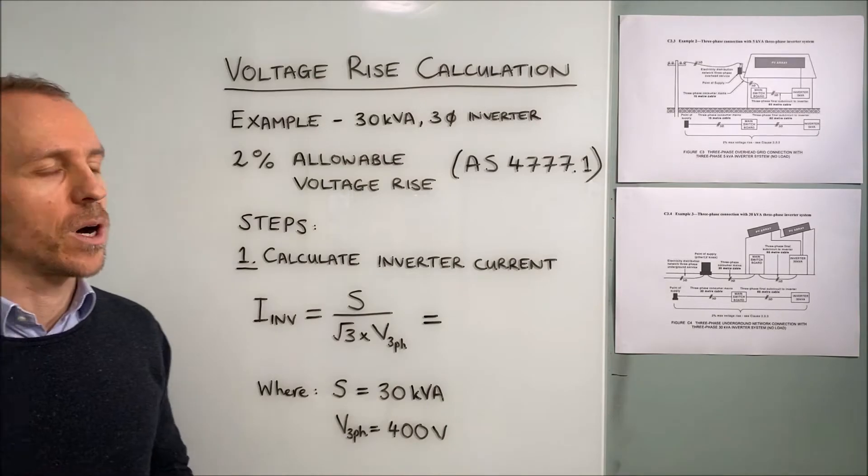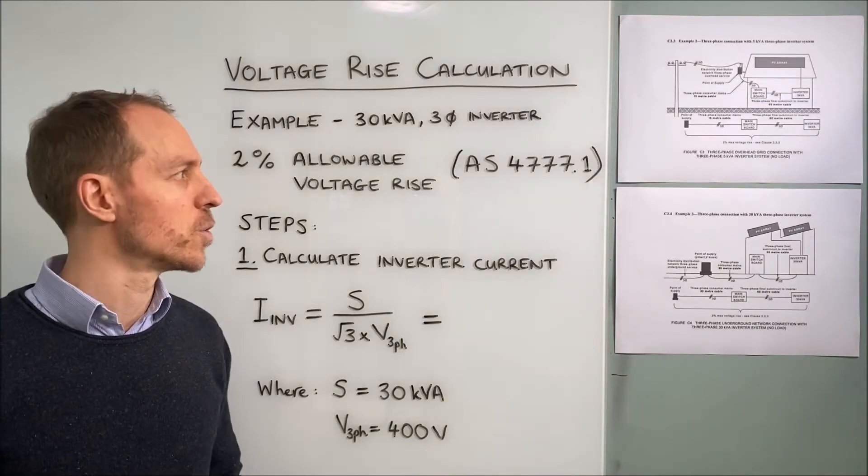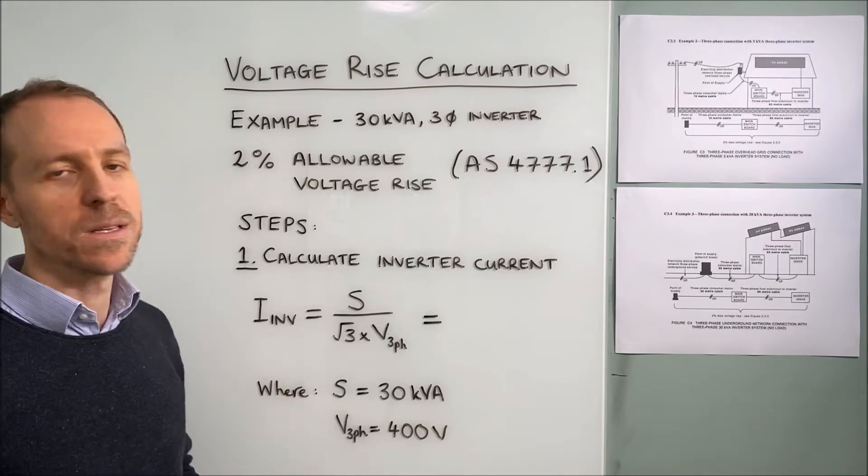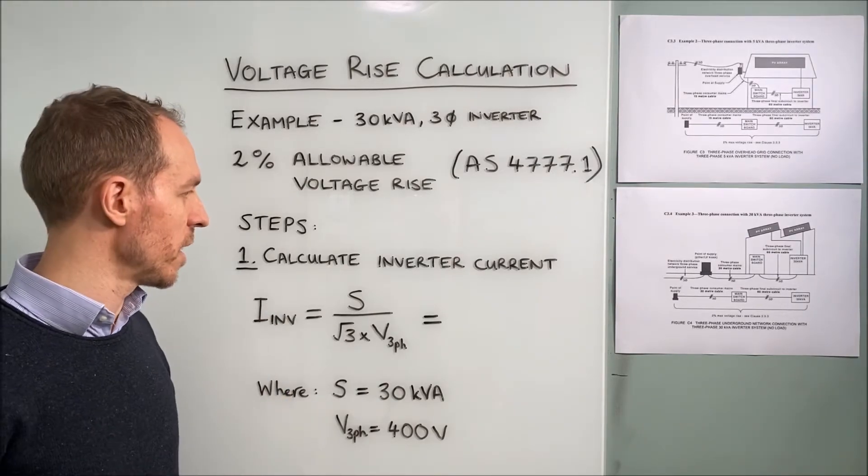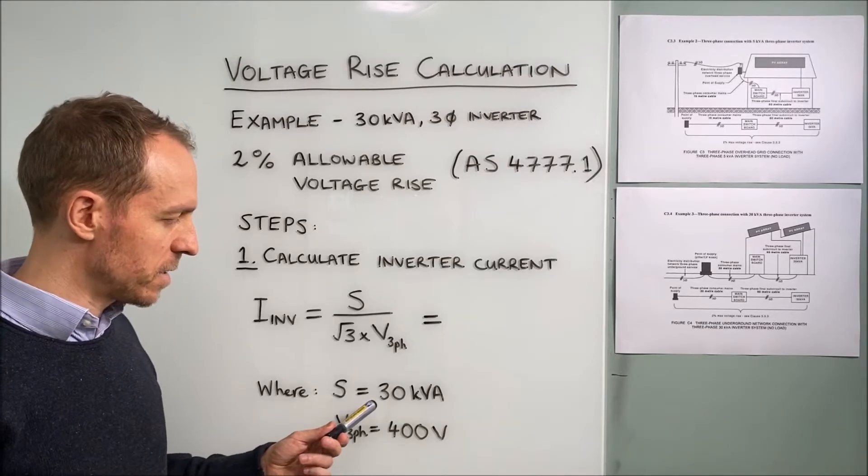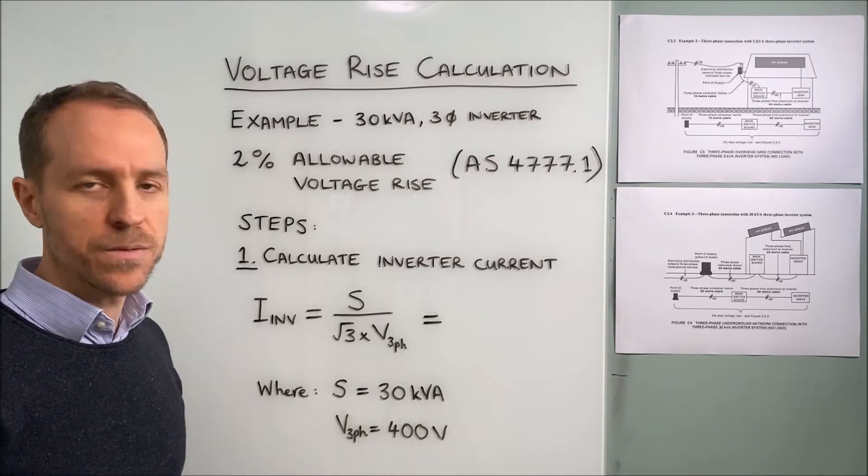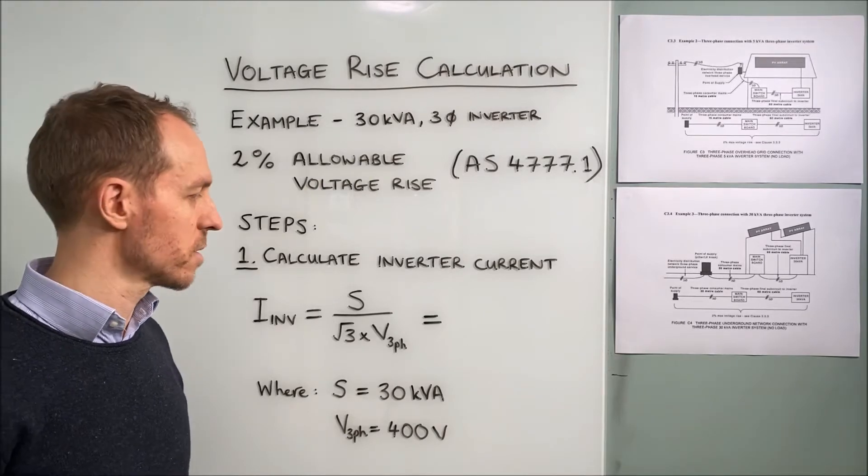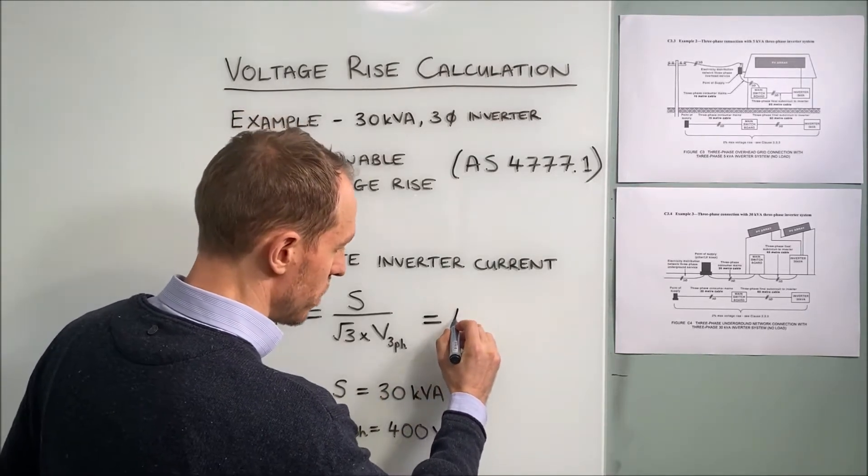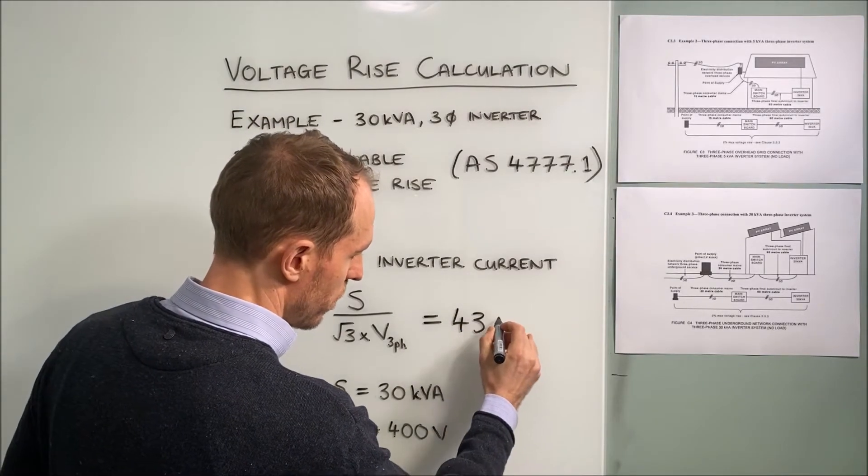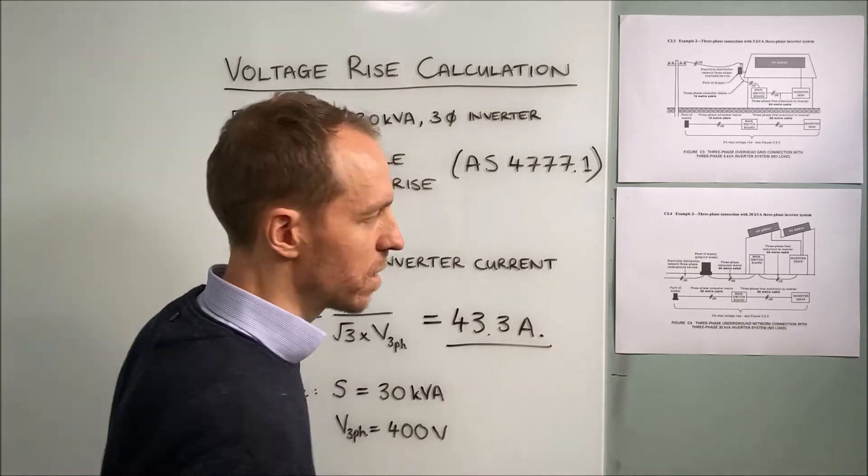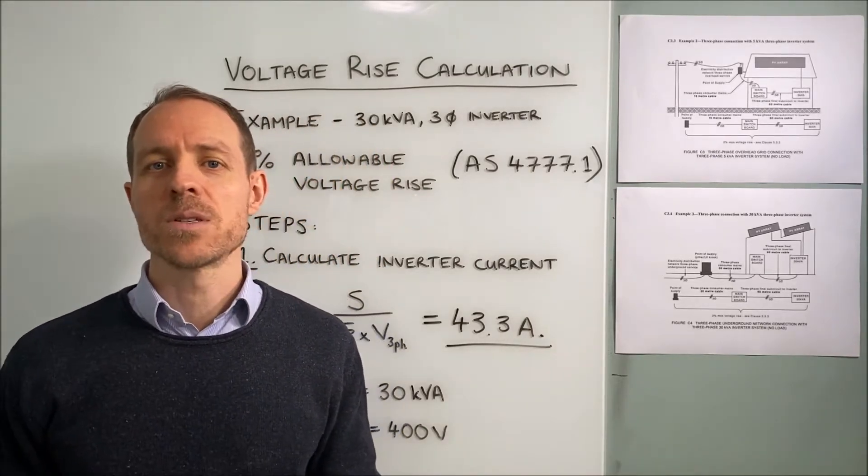The allowable voltage rise limit according to AS4777 is 2%. The first step to the calculation will be to calculate the inverter current. Based on its output of 30kVA and a three-phase voltage of 400 volts, the inverter output current is going to be 43.3 amps. We're going to use that to base our cable size calculations.